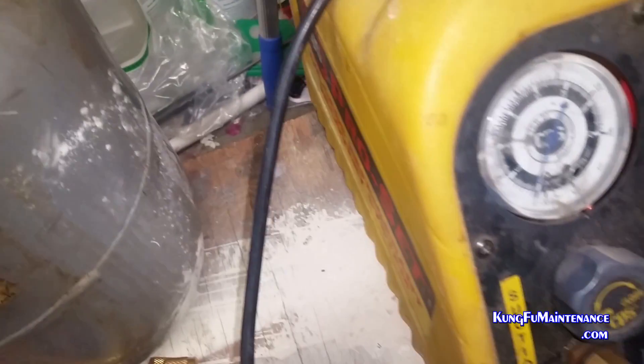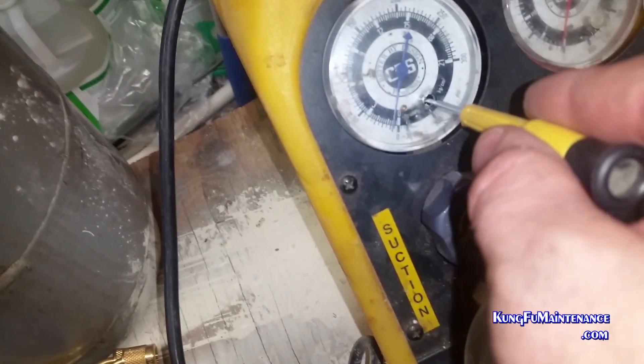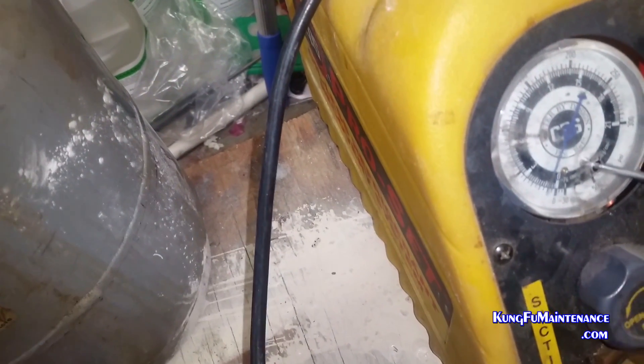We want to measure and set zero when it's at zero. That's the same with gauges — anytime that you're zeroing gauges, you're going to want to remove the pressure and make sure that there's zero pressure on those lines, and then we're setting it to zero so that we can show what's actually in the system when we hook anything up.